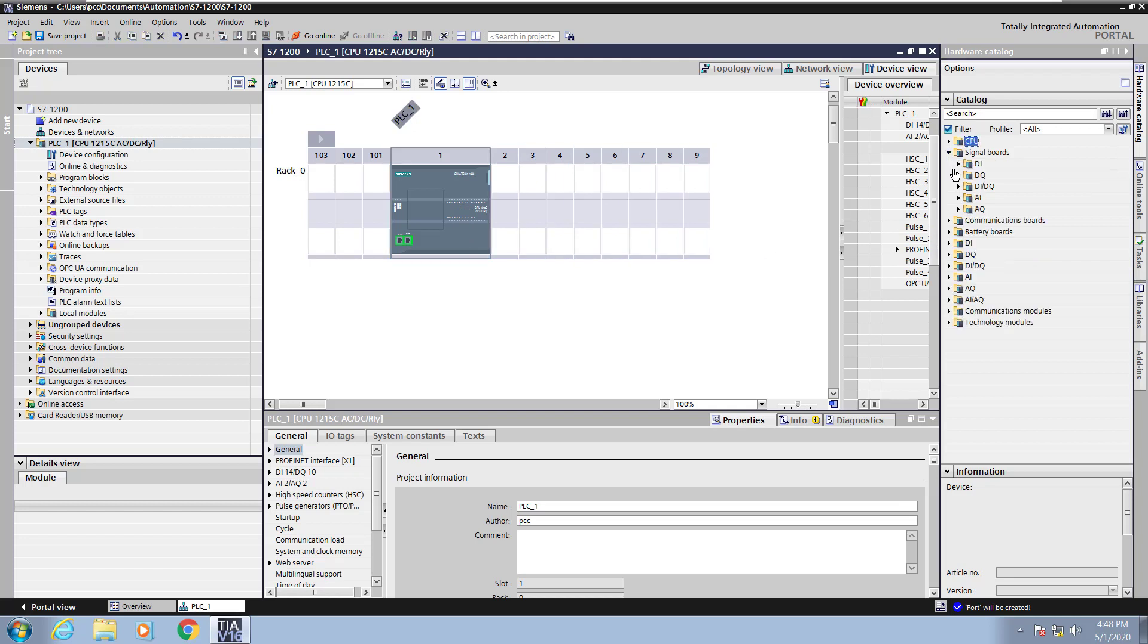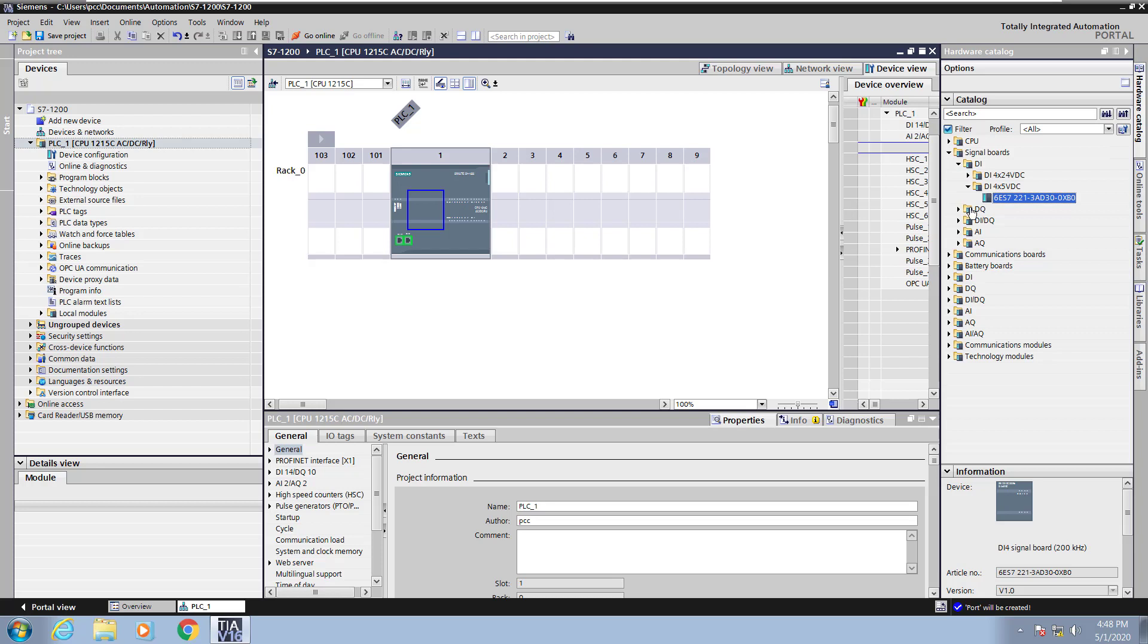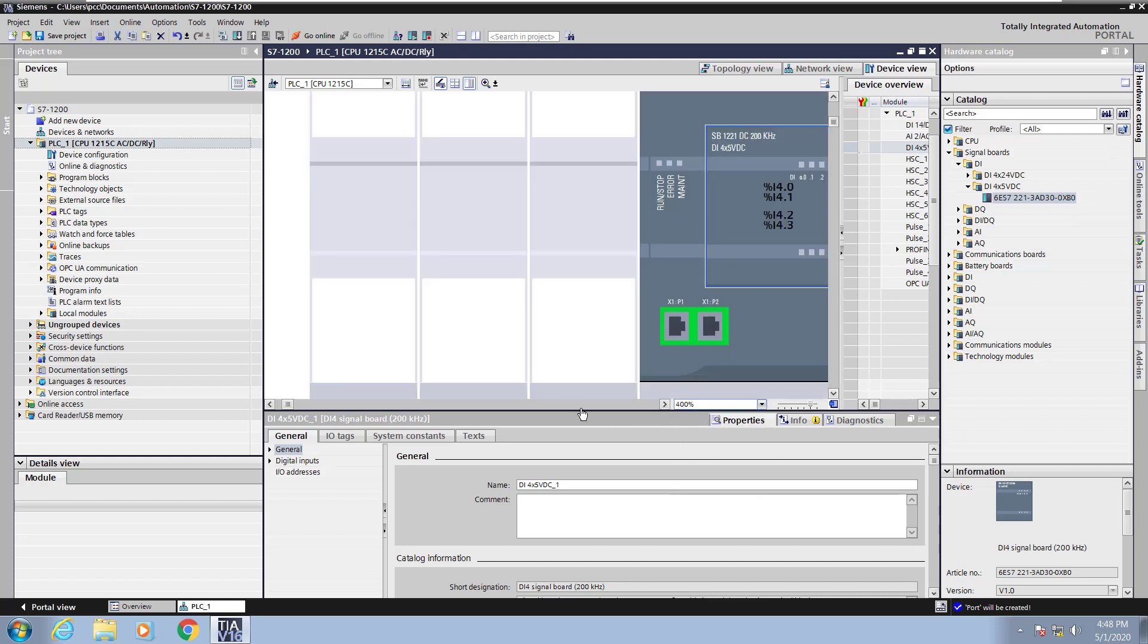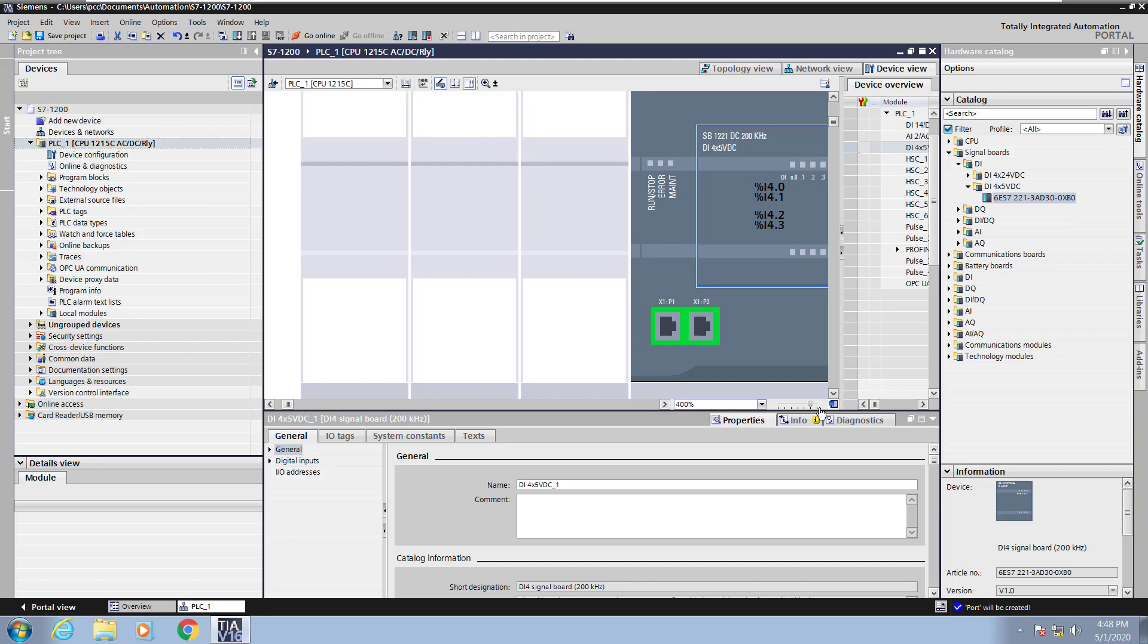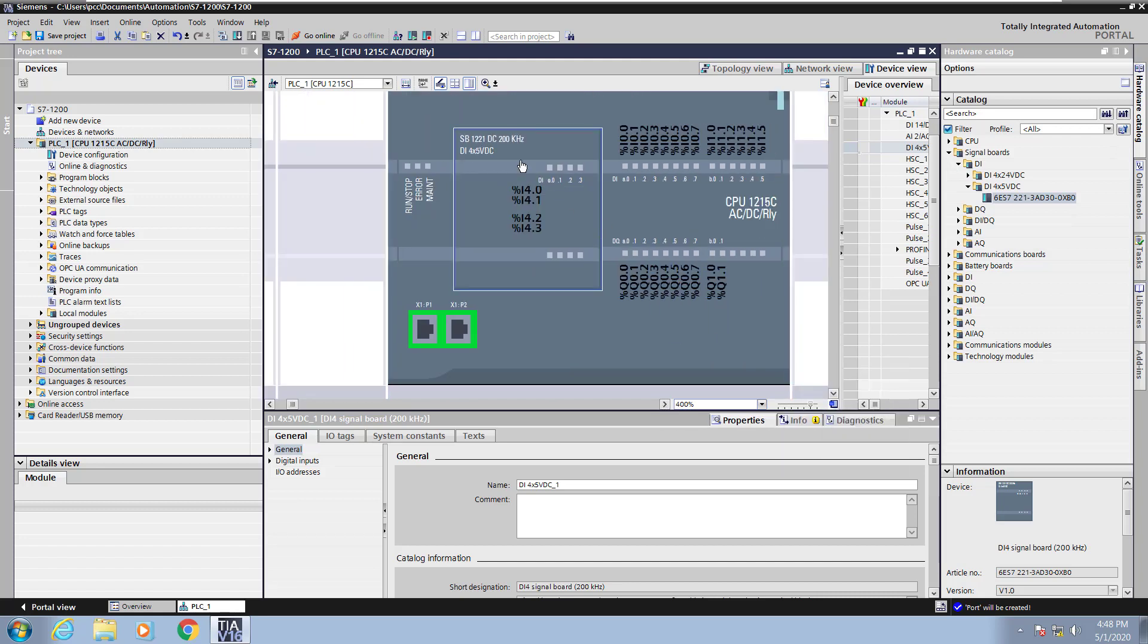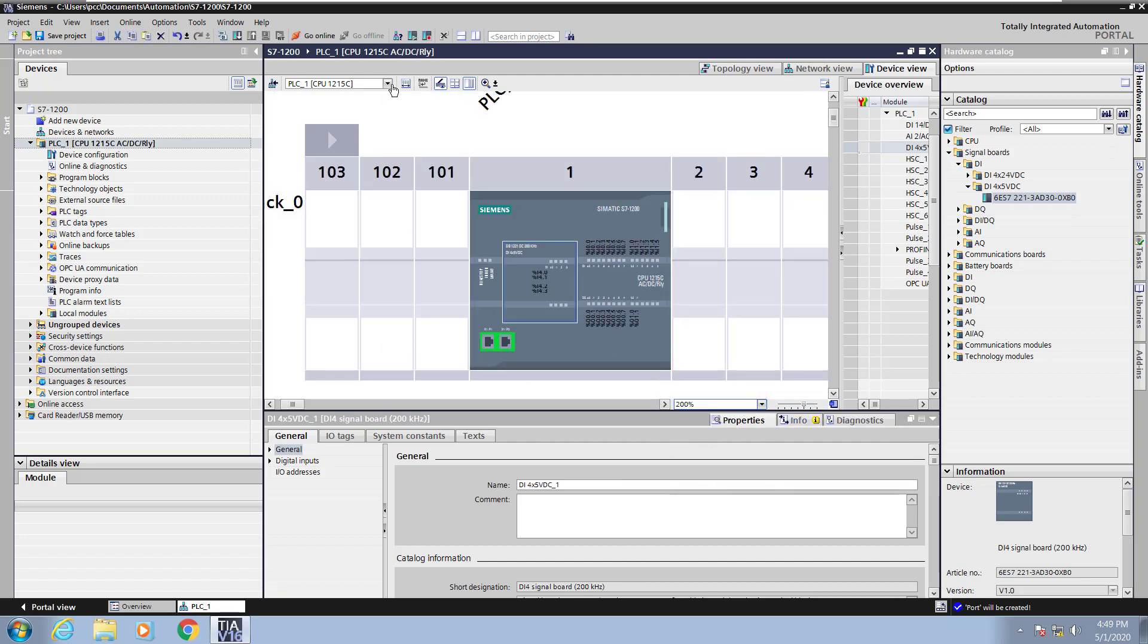Next I will show you the signal board area. So I'm going to select a digital input signal board that has four digital inputs. I'll select the part number and you can see the location of where it would show up in the hardware configuration. So I'll just drag that over and drop that in. Next I will change the zoom level of my CPU so that you can see the digital inputs actually on the CPU. I'll use the pan feature to zoom over and then you can see the four digital inputs. So I added four digital input points without expanding the footprint of the CPU.